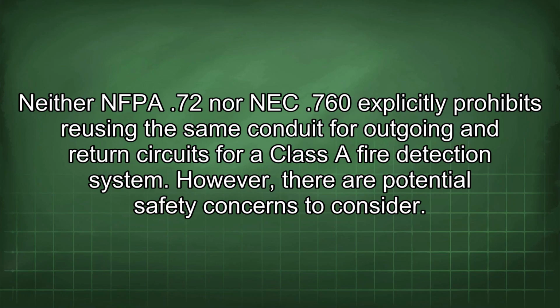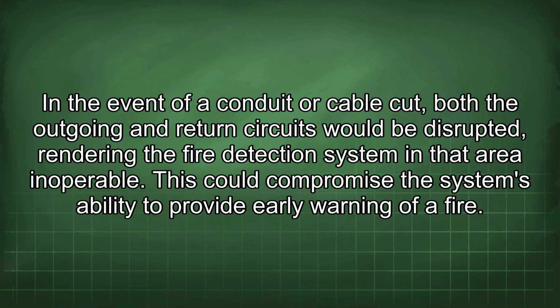Neither NFPA 72 nor NEC 760 explicitly prohibits reusing the same conduit for outgoing and return circuits for a Class A fire detection system. However, there are potential safety concerns to consider. In the event of a conduit or cable cut, both the outgoing and return circuits would be disrupted, rendering the fire detection system in that area inoperable. This could compromise the system's ability to provide early warning of a fire.